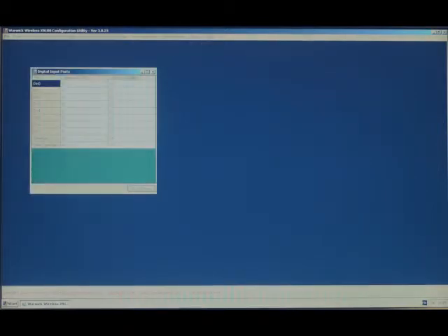The next thing to do is to configure the message which will be sent on the condition of the port. This is done by port configuration, digital port configuration, digital input ports. On D in 0 we're going to put the label. When it's high, it'll send the message open. And when it's low, it'll send the message closed. Close the box.